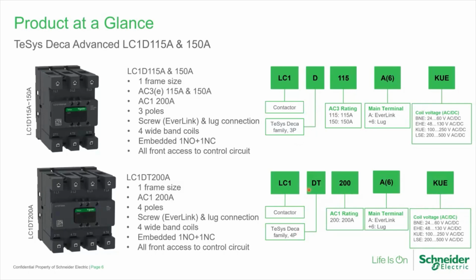The next comes the current rating. For 3-pole contactors, it is the AC3e rating that we mentioned. For 115, it will be 115. For 4-pole, it is AC1 duty. And then we'll have the termination. If it is A, it will be Everlink connections. And if you want to go for lug connection, you have to mention A6, so both the suffix A as well as 6. And then the last one is for the coil.